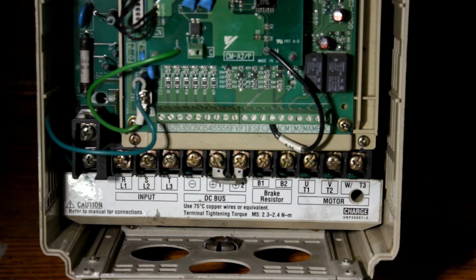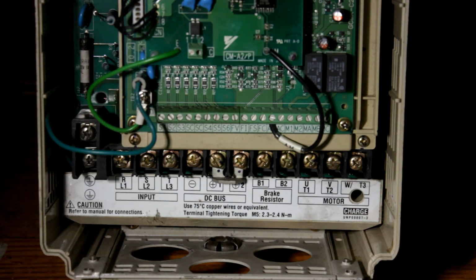Okay, guys. So this is a Magnetek GPD variable frequency drive, and as you can see, the terminals on the bottom say input L1, L2, and L3, and then in the middle it says DC bus. It has positive and negative. Then to the right of that, there's a brake resistor, B1 and B2, and then of course the motor output U, V, and W. So this type of variable frequency drive is more than likely able to be powered directly from direct current. Whatever source of direct current you have, provided it's the correct voltage, you should be able to tie directly into the DC bus through the positive and negative.